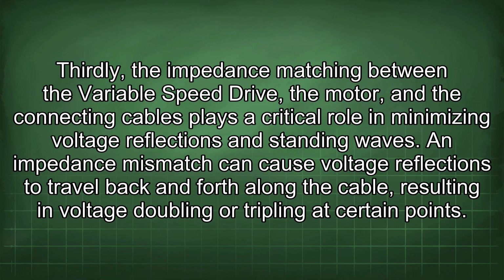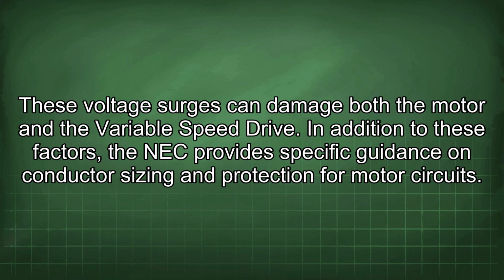Thirdly, the impedance matching between the variable speed drive, the motor, and the connecting cables plays a critical role in minimizing voltage reflections and standing waves. An impedance mismatch can cause voltage reflections to travel back and forth along the cable, resulting in voltage doubling or tripling at certain points. These voltage surges can damage both the motor and the variable speed drive.